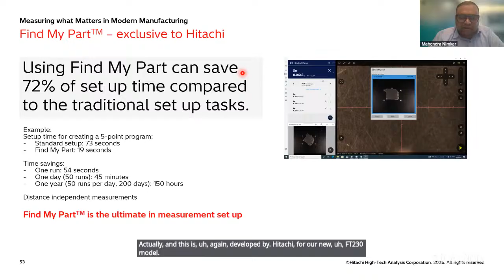It saves a lot of time, and this was again developed by Hitachi for our new FT230 model, or the FT range of instruments. And of course, as I mentioned, now the information can be transmitted to the cloud. If you activate it, a Hitachi engineer can view the service data and diagnostic data, for example, statistics for the X-ray tube or detector temperature, error logs, and so on. So even remotely, somebody can view the data and suggest what is happening with the instrument.